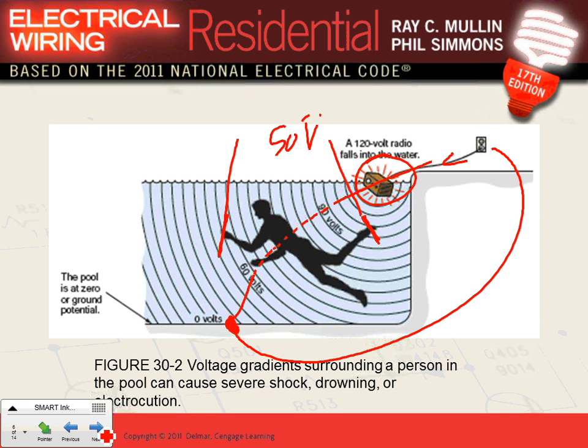When the current goes through water or through the ground, there's impedance, right? There's impedance for the water and impedance for the ground. When it goes through the ground and the water, you're going to lose voltage. So that's why the voltage closer to the source will be 90, and further away from the source will be 0. In between, there will be gradually 80, 60, 50, 40, 30. As you get close to the ground, to the shield, it will be 0. That's what they call the gradient voltage.